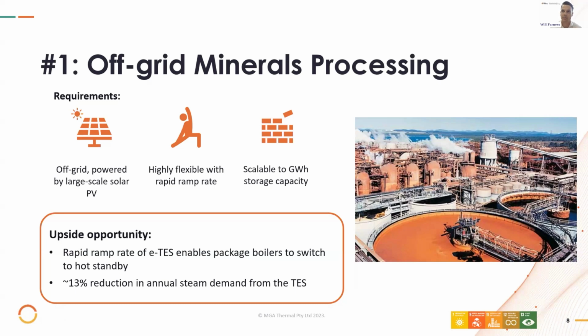Part of the problem they're facing on this site is that these package boilers are really not flexible enough for their operation. So for energy security reasons, they need to run these package boilers 24/7, idling on minimum turndown, which for context is 20 tons per hour of steam, so a significant energy load. They do that on minimum turndown so that they can rapidly ramp up steam generation in the event of a contingency. That 20 tons per hour is not being used on site, it's simply exhausted to atmosphere. So it's a massive source of energy consumption and waste heat.